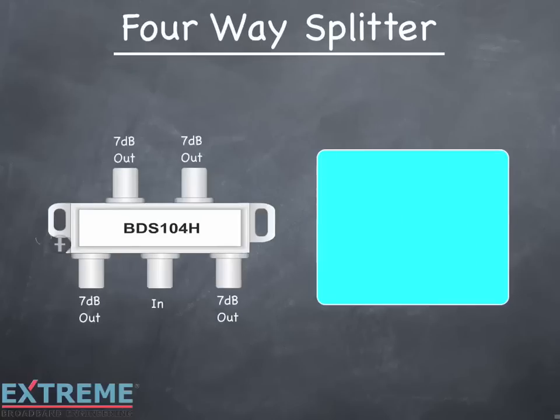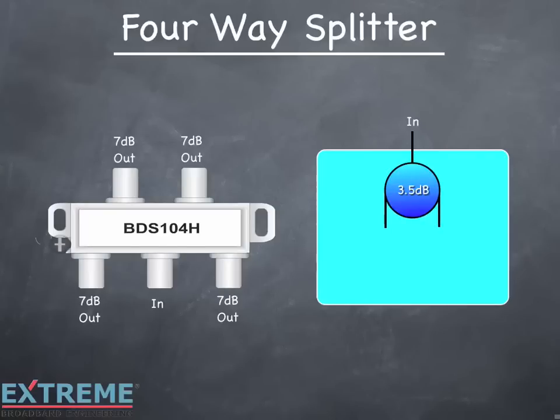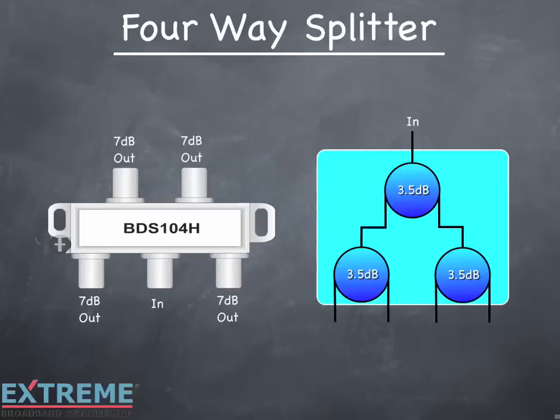On the left is a four-way splitter with all legs losing 7 dB. On the right, let's build the symbol equivalent of the four-way splitter. With the three-way splitter we saw that the 7 dB ports were made up of two two-way splitters, one feeding the other. So a four-way splitter is made up of one two-way splitter, with its two output ports each feeding an additional two-way splitter, for four ports with 7 dB of loss each.